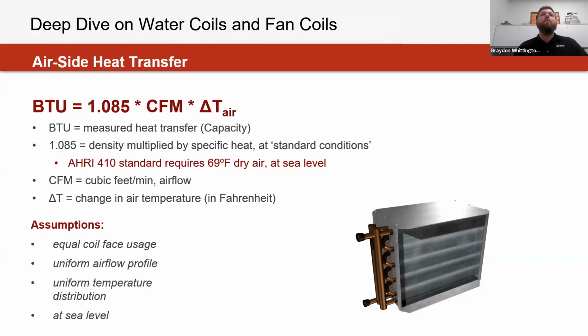And not to give PTSD of going back to the university days there, but constants have a high level of different assumptions that really go into play for making these formulas easier and simple to use. And the reality of that is that not all these assumptions are actually true of what you might see for that specific coil or the application that it's installed in, such as where it's positioned relative to sea level, how much of that coil is actually being utilized for that heat transfer that's going through it, and then even the overall profile of that air that's going to be passing through that coil there too.